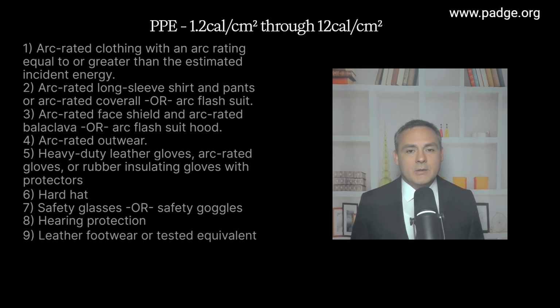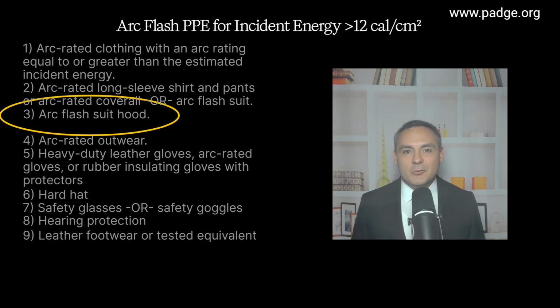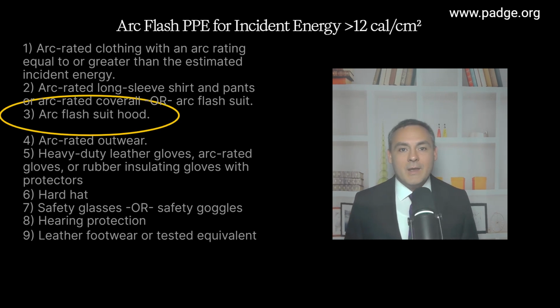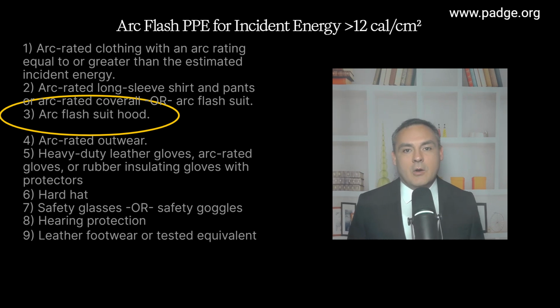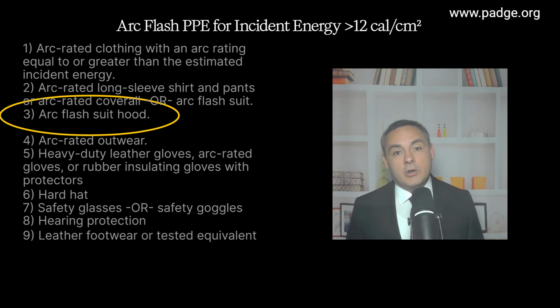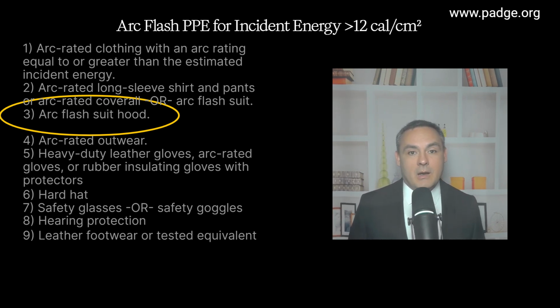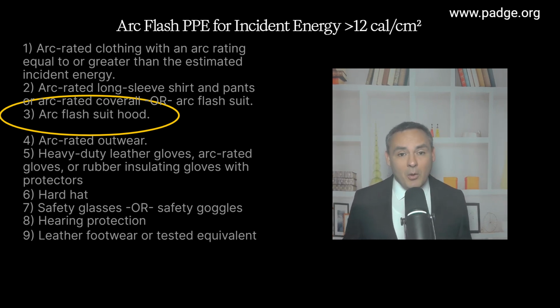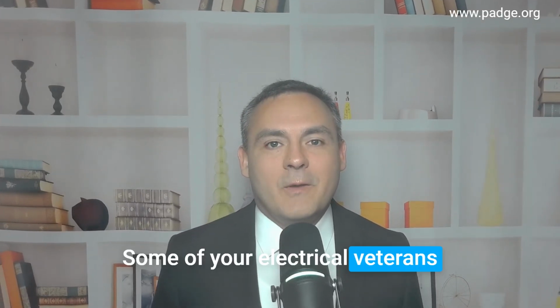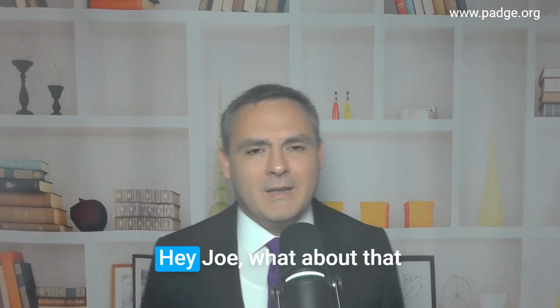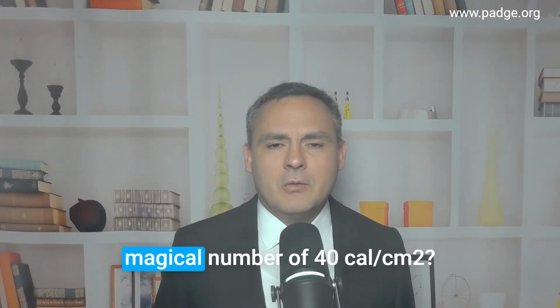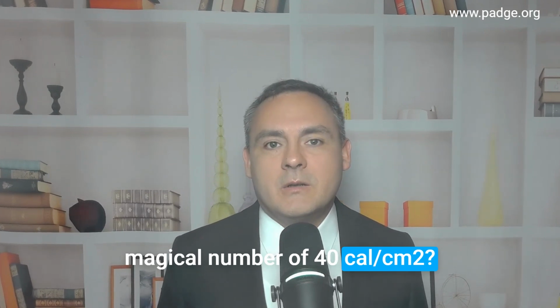Now, let's look at 12 calories per centimeter squared and up. This is where it gets really simple. Everything is the same, except you'll need an arc-rated arc flash suit hood instead of the face shield and balaclava. That's it. Simple. Some of you electrical veterans might ask me at this point, hey, Joe, what about that magical number of 40 calories per centimeter squared?